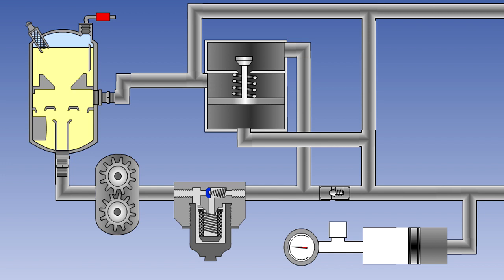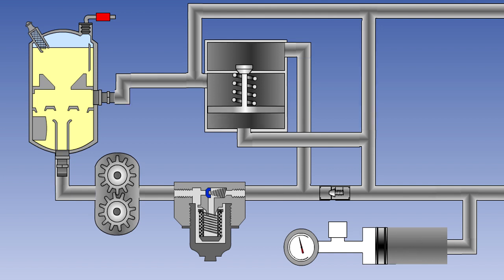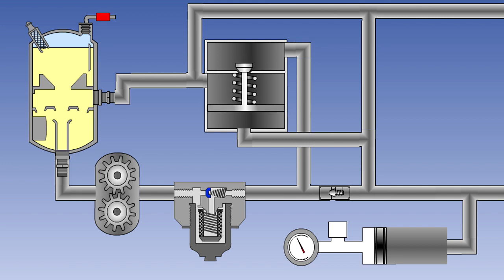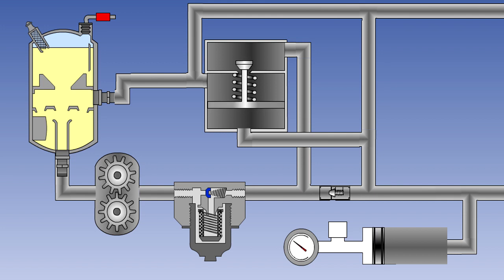Incorrect pre-charge pressure of the main accumulator can cause the automatic cut-out valve to cut in and out too frequently. This may cause rapid fluctuations of system pressure, which can be felt and heard as hammering in the system. This can rapidly cause damage to the system if it is not dealt with.